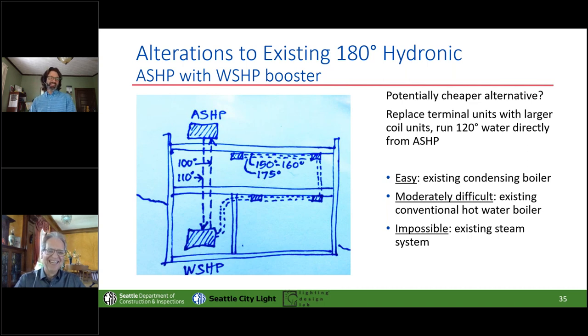So this is a cascading heat pump loop, and this is already existing technology. You've got that air-to-water heat pump, or air source heat pump, that lives outside, pulls heat from outside, puts it into water. And then you've got a water-to-water heat pump that takes that water and boosts its temperature. So right now we don't have a unit that can go from air to 180 degree hot water.